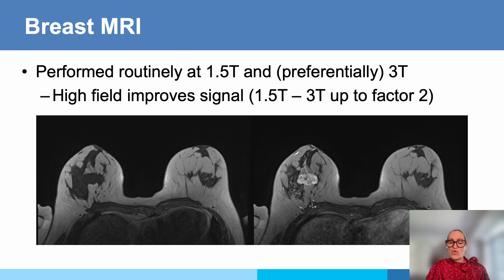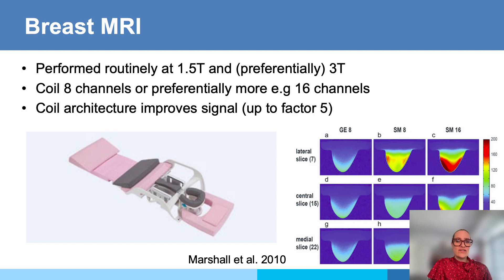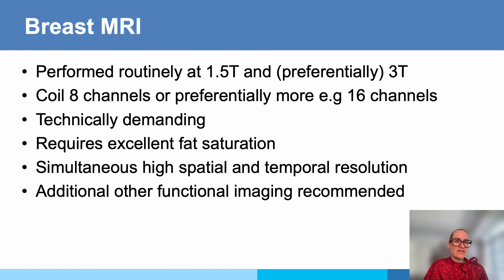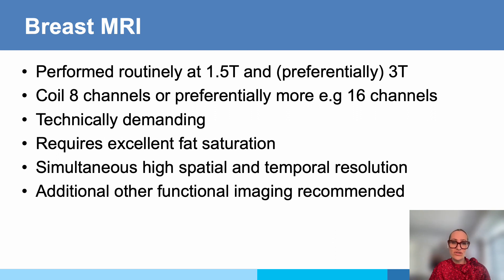We routinely perform breast imaging at 1.5 and 3 Tesla, preferentially 3 Tesla because it improves the signal up to a factor of 2. A very important part of breast imaging is the coil — we showed a 16-channel coil in our first video. We preferentially use 16 channels because it must be a dedicated breast coil, and the coil architecture can improve the signal up to a factor of 5. The minimum coil requirement is 8 channels, preferentially up to 16. It's technically demanding, requires excellent fat saturation, and we use high spatial and temporal resolution protocols and functional imaging.